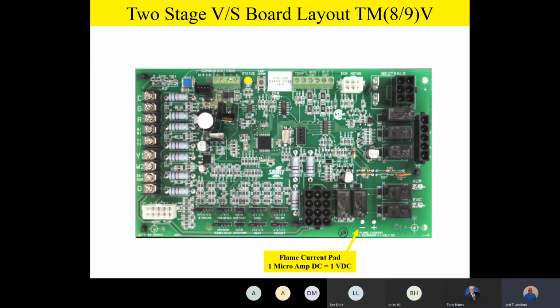Team, along the bottom of the board, we have our flame current pad. We've described that pretty thoroughly in the last couple slides. With our other boards, it's the same thing. 1 volt DC equals 1 microamp DC flame current. And the real cool thing about that is now you don't have to have a special tool or a special meter to read flame current. And by the way, I recommend on every yearly clean and check, double check that flame current to make sure that flame sensing circuitry is in good shape.